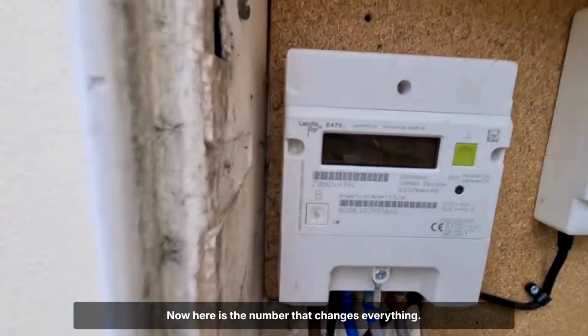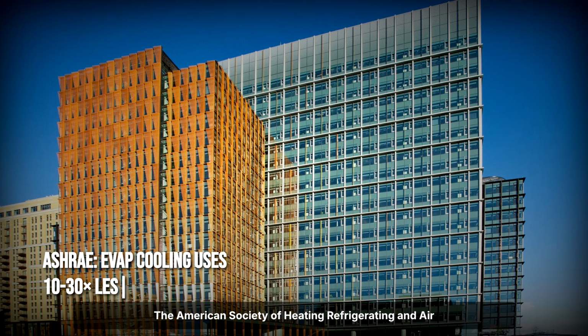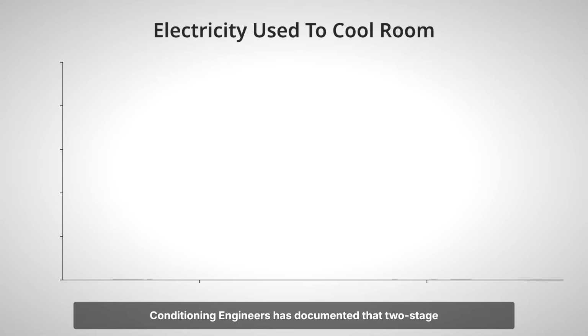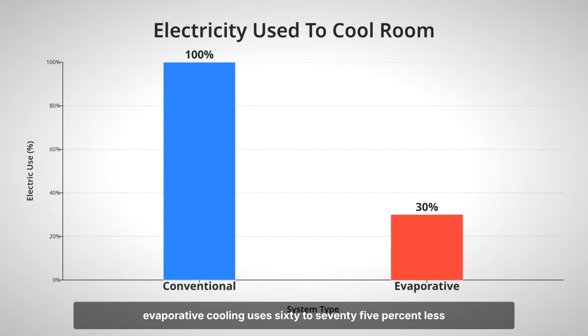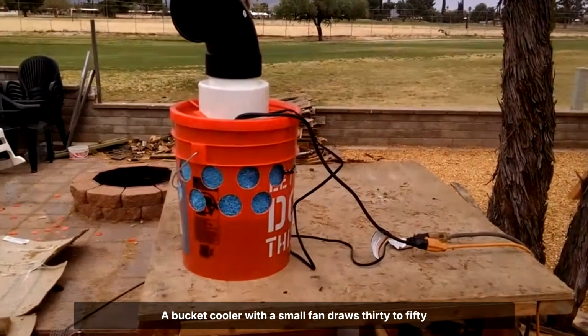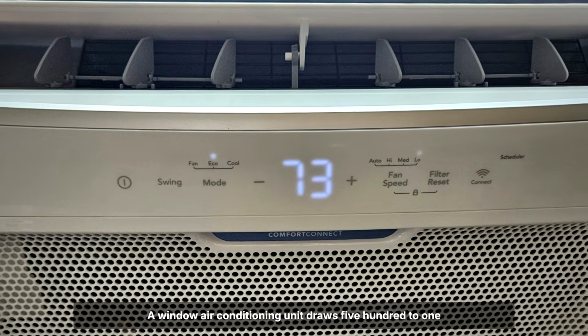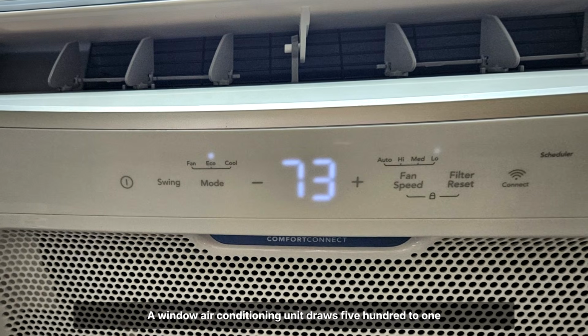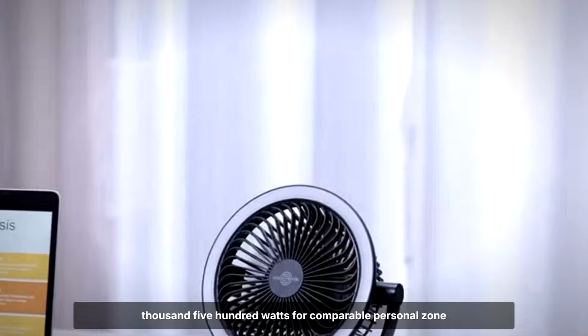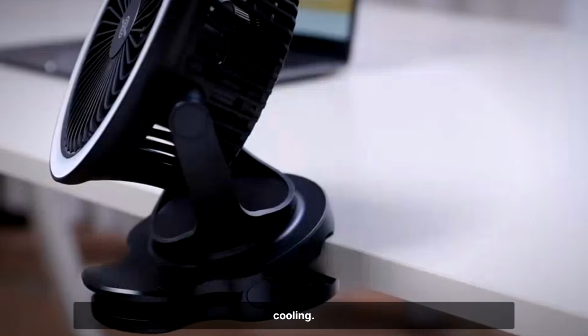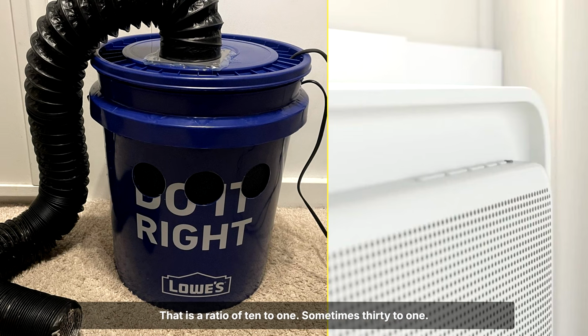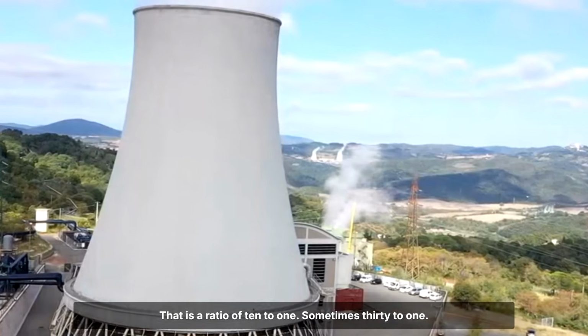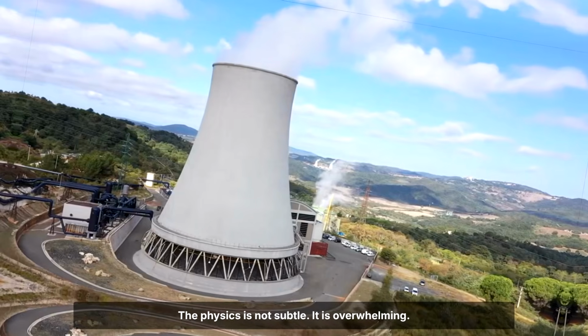Now here is the number that changes everything. The American Society of Heating, Refrigerating, and Air Conditioning Engineers has documented that two-stage evaporative cooling uses 60 to 75% less electricity than conventional refrigerant-based systems. A bucket cooler with a small fan draws 30 to 50 watts. A window air conditioning unit draws 500 to 1,500 watts for comparable personal zone cooling. That is a ratio of 10 to 1, sometimes 30 to 1. The physics is not subtle, it is overwhelming.